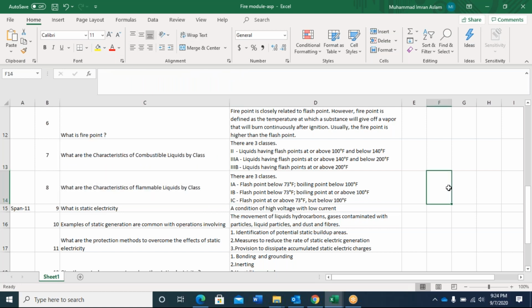For combustible liquids we usually take the flash point only. Class 2 has flash points at 100 degrees Fahrenheit and below 140 degrees Fahrenheit. Class 3A has flash points above 140 and below 200 degrees Fahrenheit. Class 3B is any liquid with a flash point at or above 200 degrees Fahrenheit.